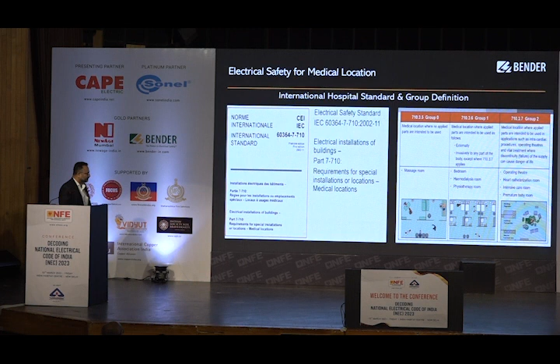So this is the chart, and on the other side we have given this chart of NEC, 2011 edition, where you can see the group 2 locations. All the anesthetic rooms and operation theaters, everywhere, it has given that continuity of power supply has to be maintained. In NEC it was given as a P7 location, or sorry, this is a P5 location. Continuity of power supply should be maintained in case of an earth fault also, an insulation fault.